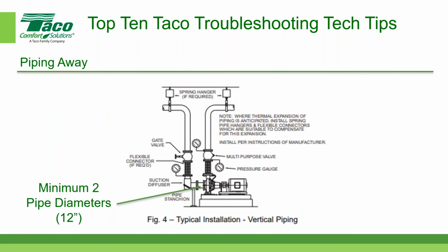Okay, this is the end suction diffuser. If we can get it, we'd like to get a spool piece between the suction diffuser and the inlet of the pump. We know that that's not necessarily a practical solution. We're happy to mount the suction diffuser directly on the pump. But anything that we can get that's a straight run of pipe between the suction diffuser and the inlet of the pump is going to improve the performance of the pump. Now, when it comes to an end suction diffuser, the performance doesn't degrade by that much. We know this because we've done some recent tests in the test lab with and without suction diffusers, and it does make a slight difference, but it does not have a major impact on the operating characteristics of the pump. So these are sort of ideal conditions that would be nice to have.